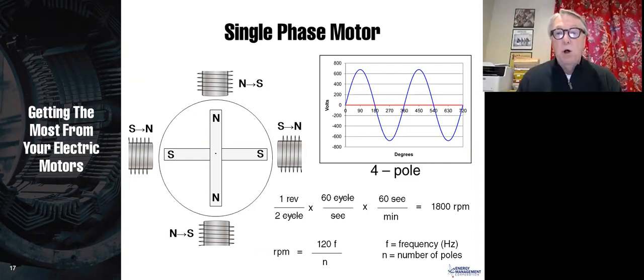Now, how many poles can we put on a motor? The answer is as many as we want. And so the more poles we put on the motor, the slower that motor runs at 60 hertz. And the formula for that is 120 times the frequency divided by the number of poles.